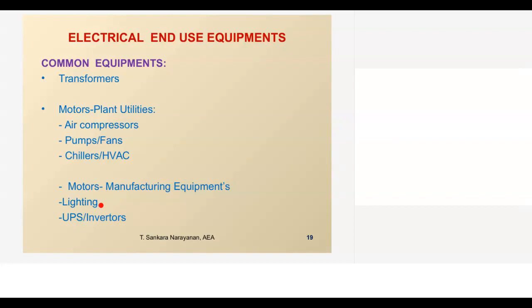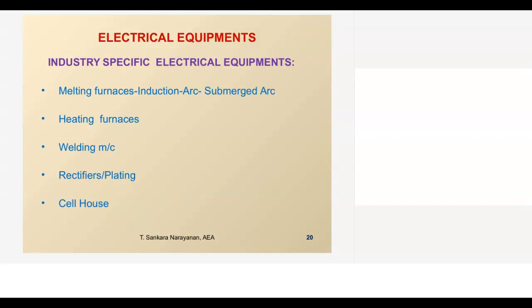Lighting is common. A lot of changes have taken place in lighting after LED. Then UPS and inverter loads are also slowly increasing in most places because of the data analysis and data requirement. Then industry specific equipment, like in the steel industry, there is the melting furnace. It can be an induction, arc or a submerged arc. Submerged arc is basically for ferrosilicon and ferromanganese manufacturing. Induction furnaces are predominantly used in most of the secondary steel melting.